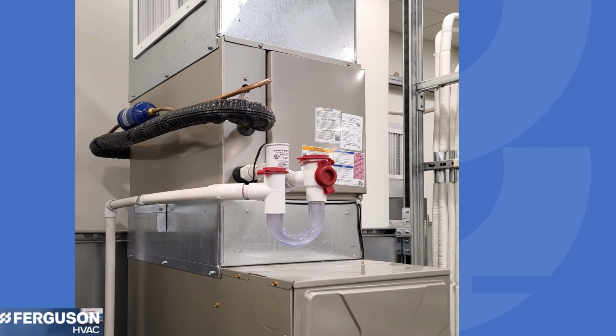Whenever we're designing a system with a coil, we want to smooth out the airflow before it gets to the coil. So a transition, as much space as you can give us, will smooth the air out coming out of the air handler or furnace and completely bathe the evaporator coil in smooth, good air to get the highest efficiency we can out of that system.